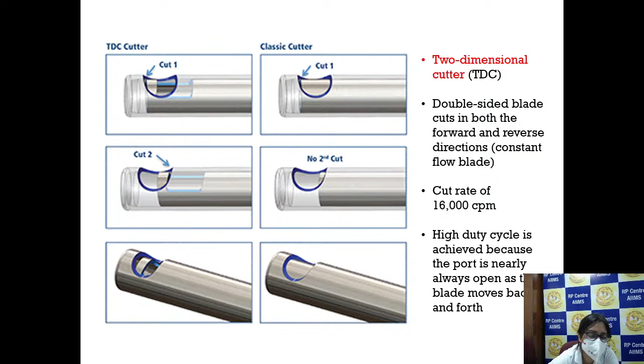So in the vitrectomy cutter, because of the recent modifications, some problems have also arisen, like the rigidity of the cutter. Smaller the gauge, thinner will be the instrument, hence more malleable. Hence the new innovations came like 25 plus and 27 gauge, which have a 5 mm supporting sleeve near the proximal end to keep it straight and rigid. But it is not very effective for the 27 gauge. And they have reduced the effective length of the instrument. Like your 25 gauge was around 32 mm, and 27 gauge is around 25 mm. So reducing the length of the instrument has also increased the rigidity of the cutter. So a smaller gauge cutter like 27 gauge cannot be used in high myopic eyes.